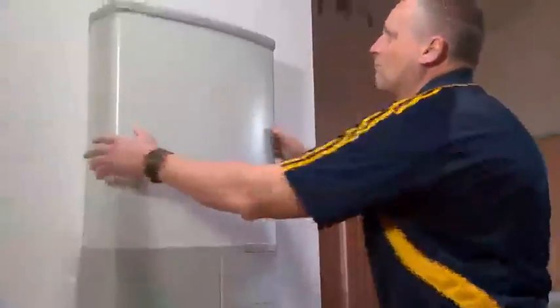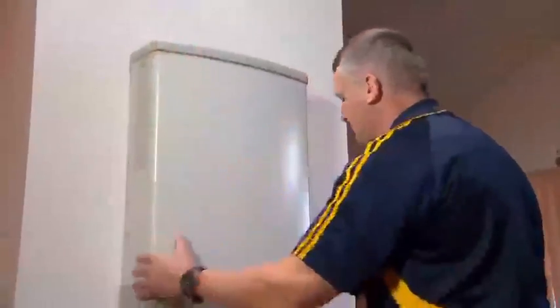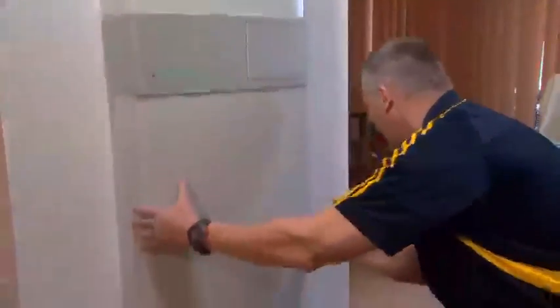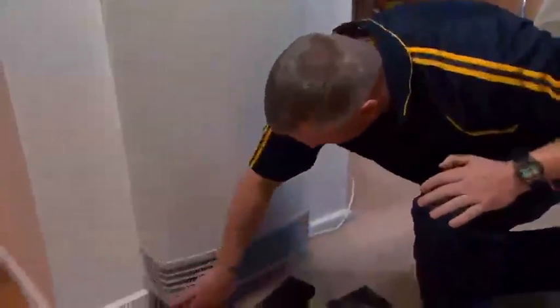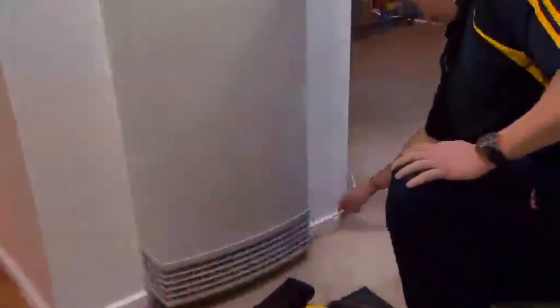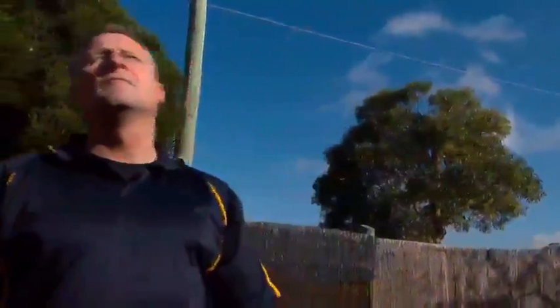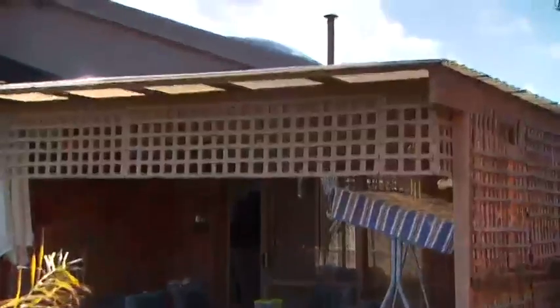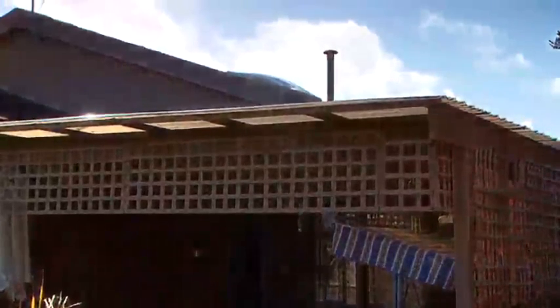Ensure all indoor gas appliances are not operating. Prior to lighting the appliance, carry out a safety and installation inspection, checking the appliance, the flue, and the ventilation available to the appliance. Note the area in which the heater is located. Also inspect the flue from the outside where possible. Look for blockages such as a bird's nest, breaks or holes in the flue, and whether the flue is in good condition.